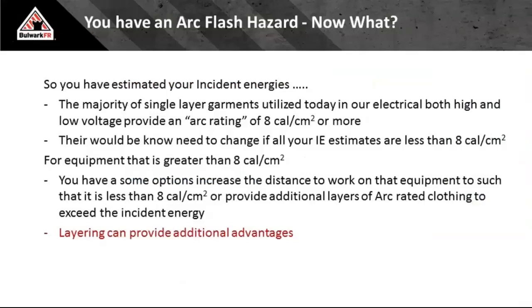So you have an arc flash hazard. Now what? You've estimated your incident energies. You have your incident energy analysis done. The majority of your single-layer garments today in most facilities are going to be 8 calories or greater. So what does that mean? That if most of my equipment is under 8 calories, then I'm wearing more than 8 calories of protection. My arc-rated clothing program is pretty much dialed in.